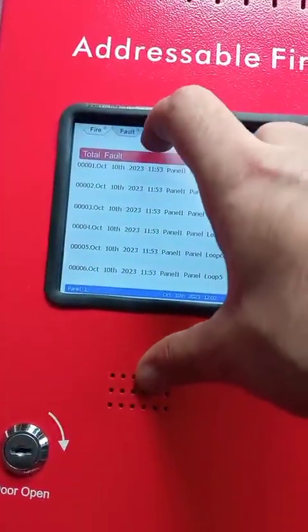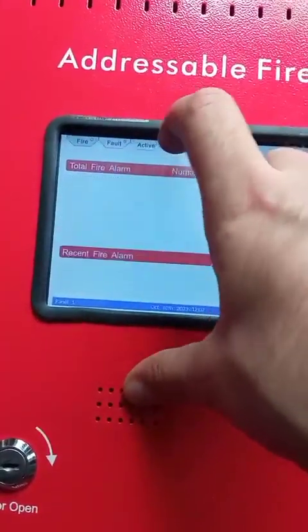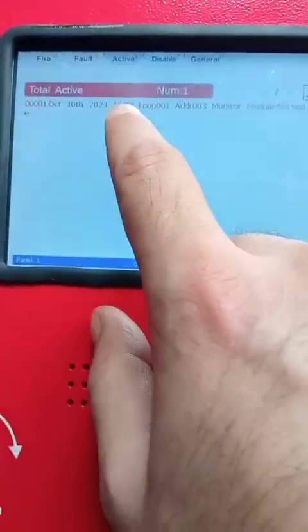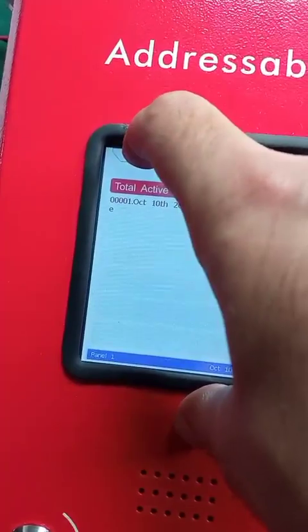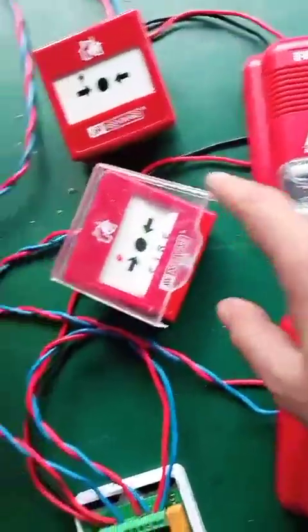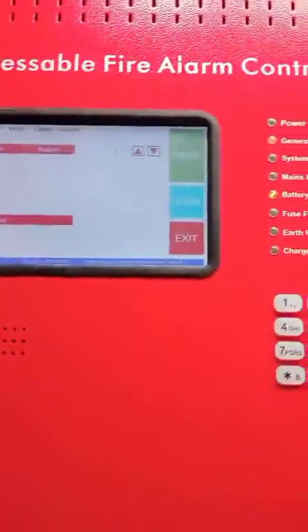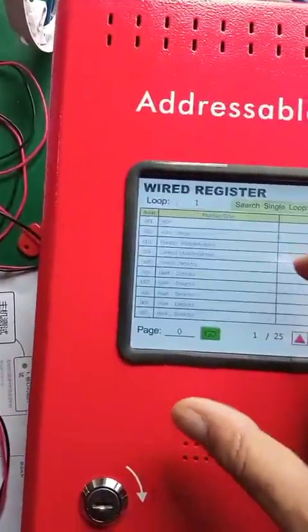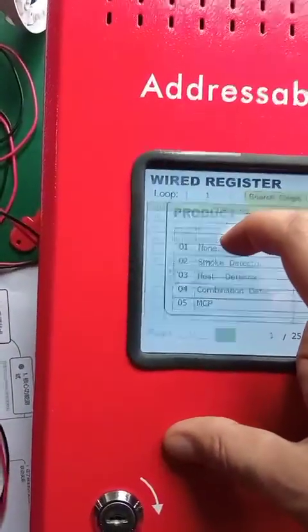You can see that it is active — the monitor module is active because there is a fire at the MCP. But there is no actual fire alarm output, only a supervisory activation, because this mode is used for supervisory only. No output devices are activated.